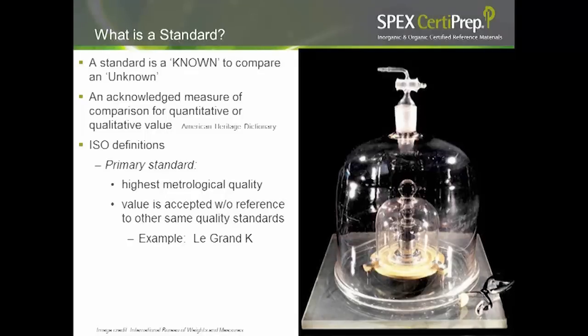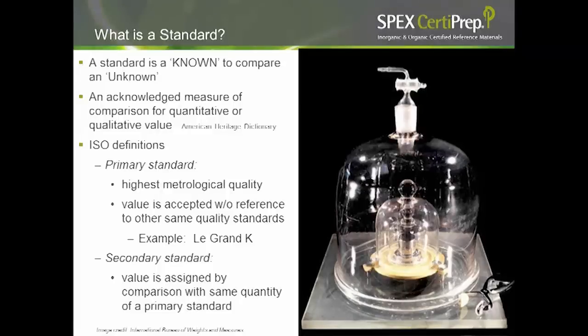The classic example has been the Grand K, or the Grand Kilogram, which was the primary standard of the kilogram housed in the International Bureau of Weights and Measures outside of Paris. Secondary standards have values assigned by comparison with the same quality and quantity of a primary standard. There is a national measurement institute for each country under primary standards — in the United States it is NIST, in Canada it is NRC, and in the United Kingdom it is NPL. Your CRMs would fall under secondary standards related to primary standards.